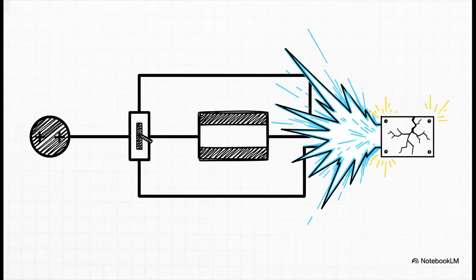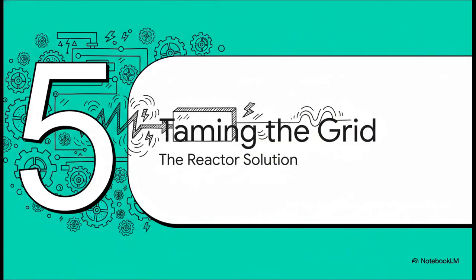These power capacitors are vital for keeping the grid's voltage nice and stable. But when you switch one on, it acts like a bone-dry sponge hitting water, trying to soak up a massive amount of electricity all at once. This creates what's called an inrush current, and this surge can be so powerful it can literally damage other equipment on the grid.